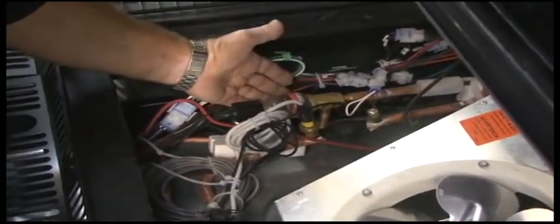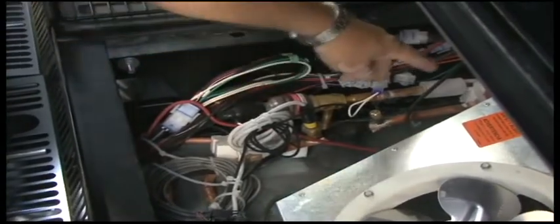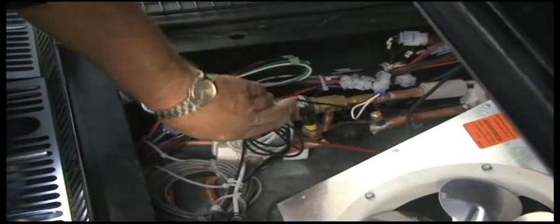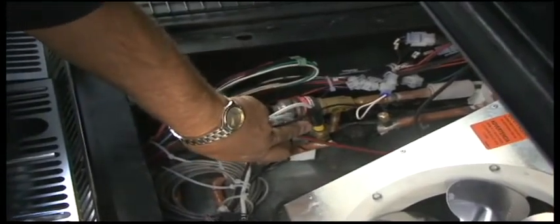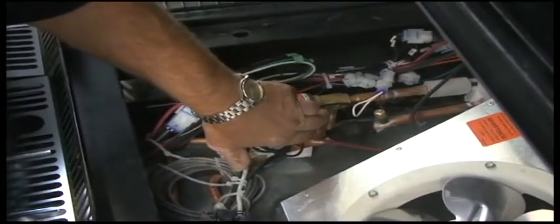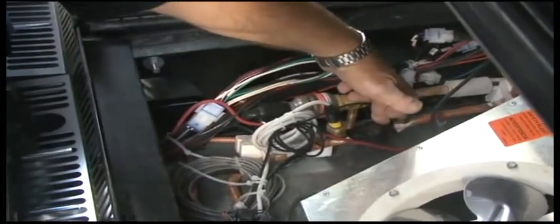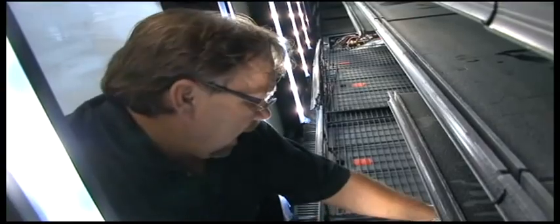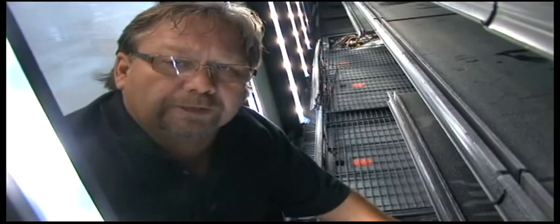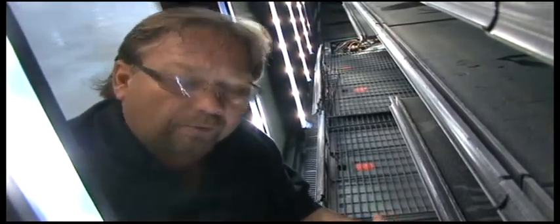Next, we have our temperature probe located here on the suction line. We also have our pressure transducer next to the suction line. The temperature probe is located on the suction line returning from, leaving the coil going back to the compressor — we're going to look at the suction temperature here. Then we have the pressure transducer, which is a 0 to 500 PSIG unit. We're using 0 to 500 because this is a CO2 system and the suction pressure runs around the 200 pound range.